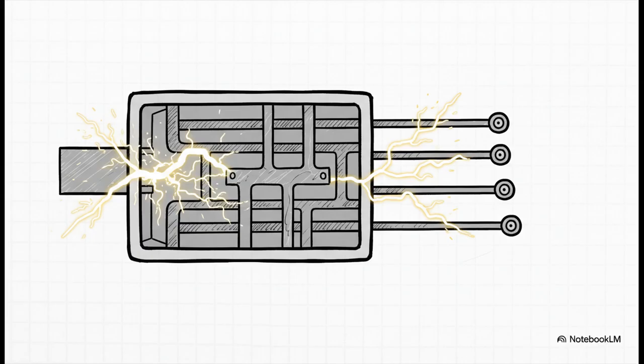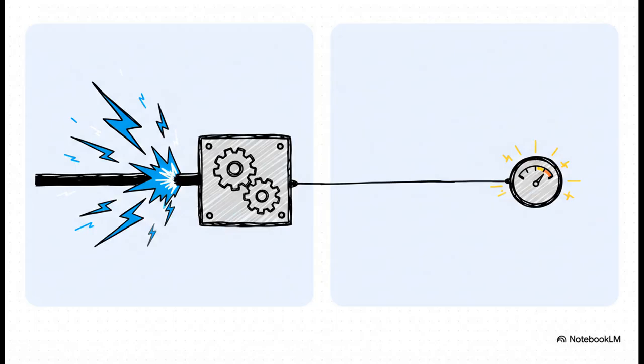So here's a question: how do you measure thousands of volts and amps without completely vaporizing your instruments? Well, the simple answer is you don't do it directly. Instead, HV systems use these brilliant devices called current transformers and voltage transformers. Think of them like a gearbox for electricity. They step down the current and the voltage to safe, tiny, measurable levels that all the meters and protective relays can easily read. It's pretty genius, actually.